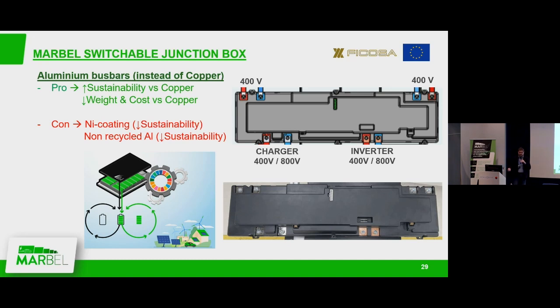Obviously, as mentioned, we need coating here. Why do we need coating? Because our busbars are made with aluminum, but they have to be connected to copper-based busbars on components like relays, contactors, and so on. So that's a problem: what to do with the alumina layer that instantly forms on the surface of the busbars? That's the first issue also mentioned before.